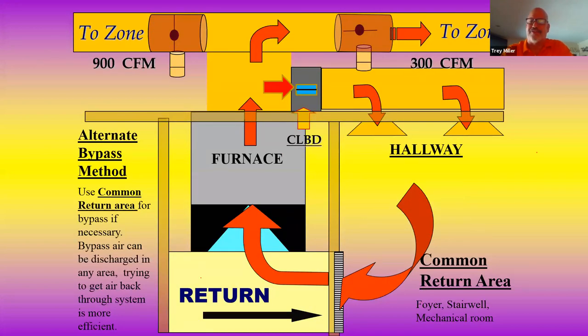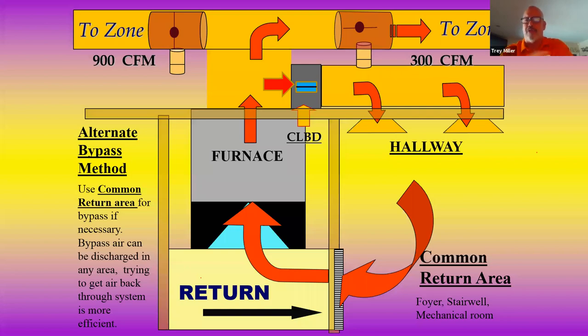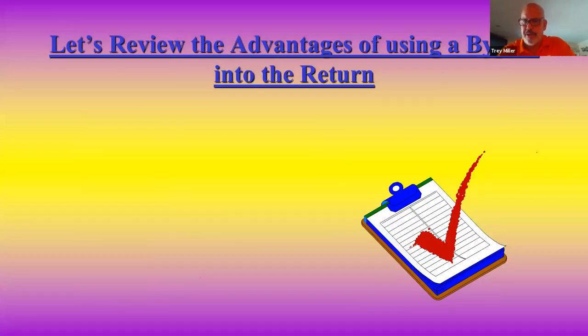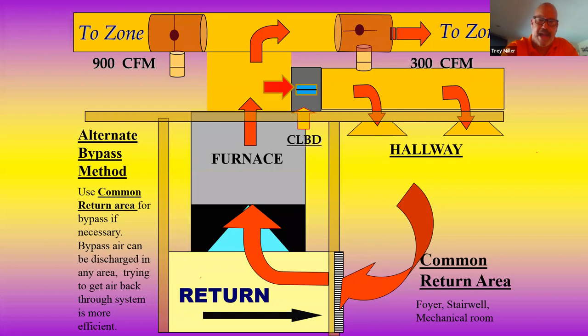Makes it very nice as far as the way this goes. And let me tell you, you can do this in any job. Just make sure you get that bypass air where you need it. Now, guys, you can run a bypass anywhere you want, but the most efficient thing to do is to get it back across the coil. That's pre-cooling the coil, preheating the coil, reducing the runtime.